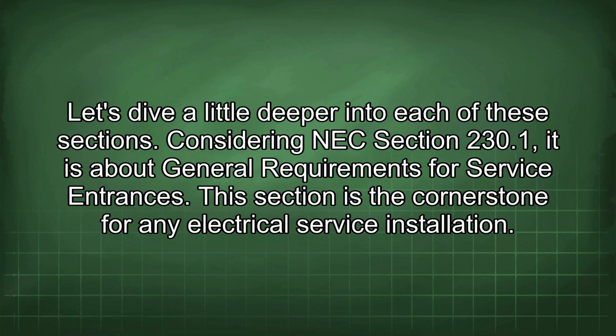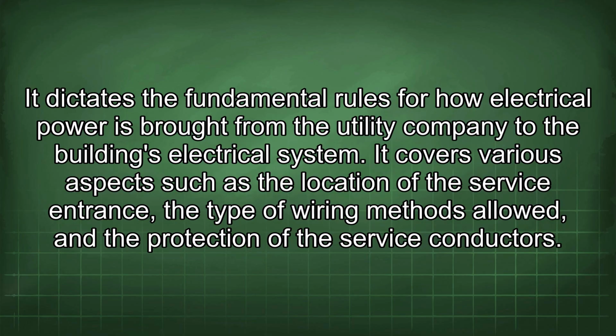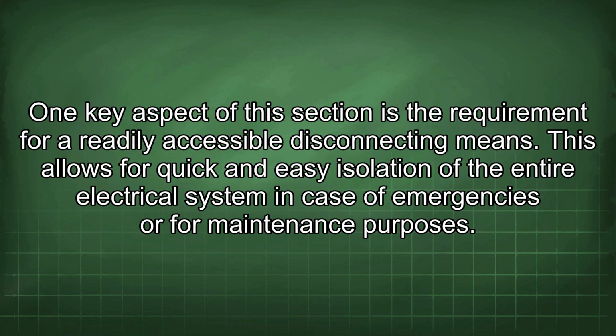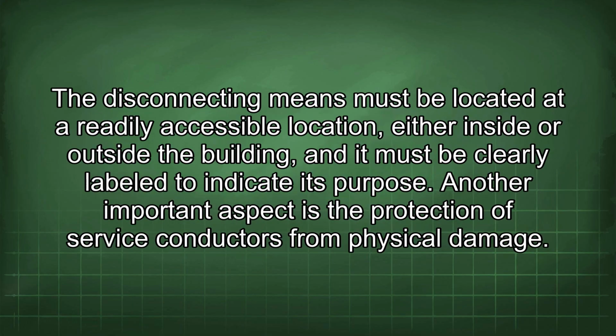Considering NEC section 230.1, it is about general requirements for service entrances. This section is the cornerstone for any electrical service installation. It dictates the fundamental rules for how electrical power is brought from the utility company to the building's electrical system. It covers various aspects such as the location of the service entrance, the type of wiring methods allowed, and the protection of the service conductors. One key aspect of this section is the requirement for a readily accessible disconnecting means. This allows for quick and easy isolation of the entire electrical system in case of emergencies or for maintenance purposes. The disconnecting means must be located at a readily accessible location, either inside or outside the building, and it must be clearly labeled to indicate its purpose.